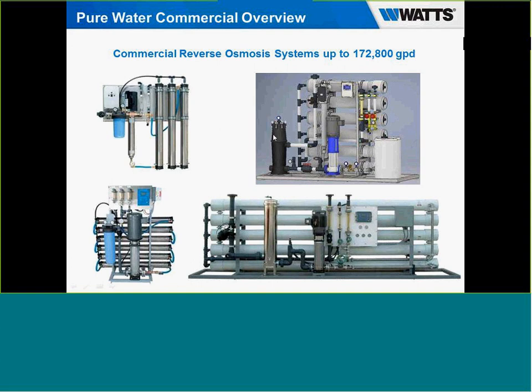And these will have this big bubble housing here for sediment. It's one large cartridge that goes in here for sediment reduction. We have a UV system. It's hard to tell what's the chamber right here with the black control box. You can put that on the inlet or the outlet of the RO system depending on the application of water quality. The reason why you put the UV system on the inlet of the RO system is to remove any microbiologicals in the water that could slime over the RO membrane, then it wouldn't produce enough RO water per day. So you can use it as either a post or pre-treatment.